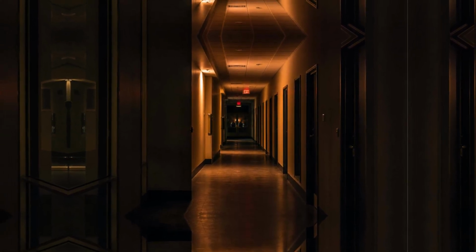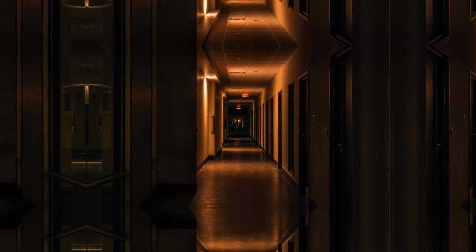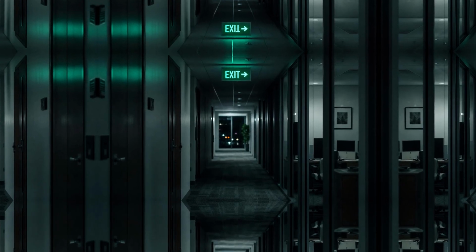Emergency circuits must be kept separate from normal power circuits, not loosely separate, not separated wherever convenient, genuinely, physically, consistently separate, in their own conduit, on their own wiring pathways, protected by their own devices, served by their own panels. Separate enough that a failure in the normal power system cannot reach across and affect the emergency system. Separate enough that a fault in a normal circuit cannot take down an emergency circuit at the same time. The reason for this separation is straightforward when you consider the alternative.